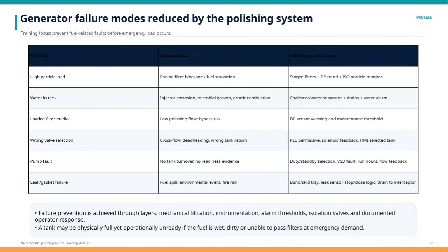Here, we're focusing on how the fuel polishing system helps reduce generator failure modes by preventing fuel-related faults before an emergency load situation arises. The key to this is understanding the various fuel risks and their consequences, and how we control these through multiple layers. For example, a high particle load can block engine filters and cause fuel starvation. To control this, we use staged filters along with differential pressure trend monitoring and ISO particle counters.